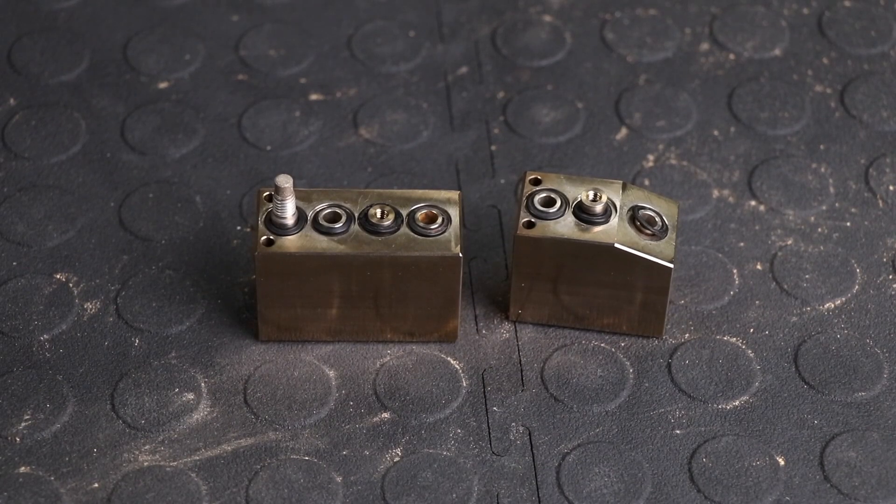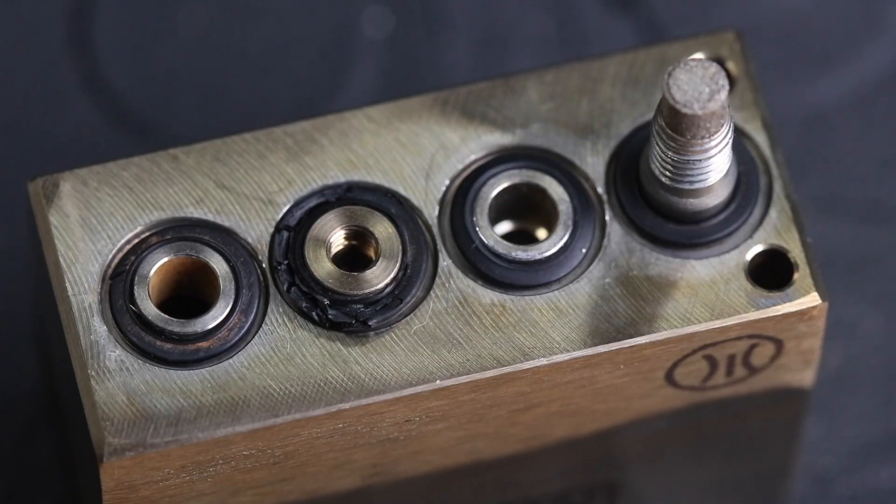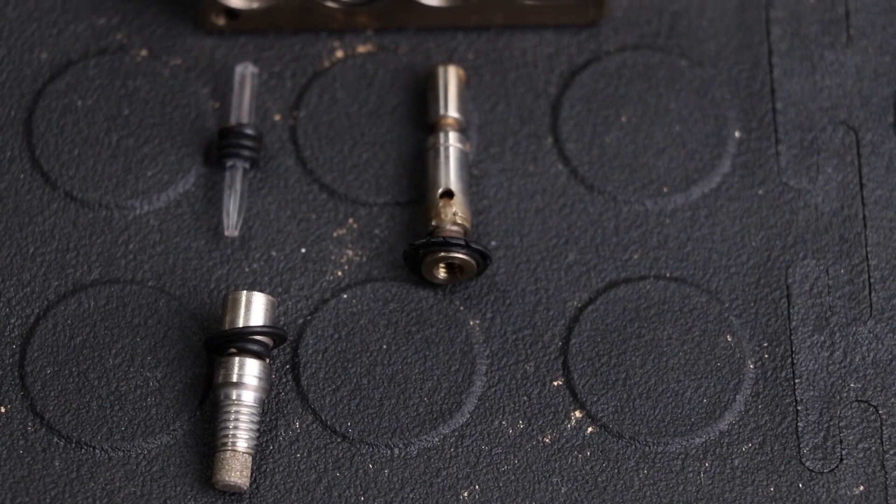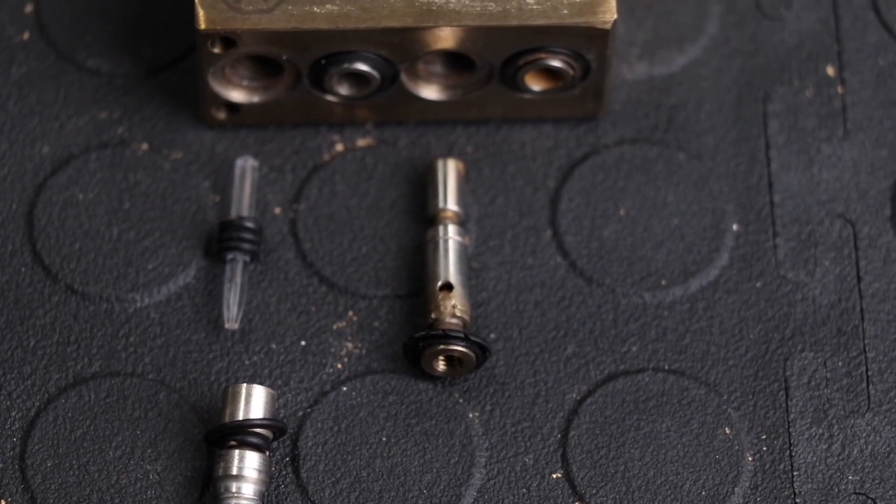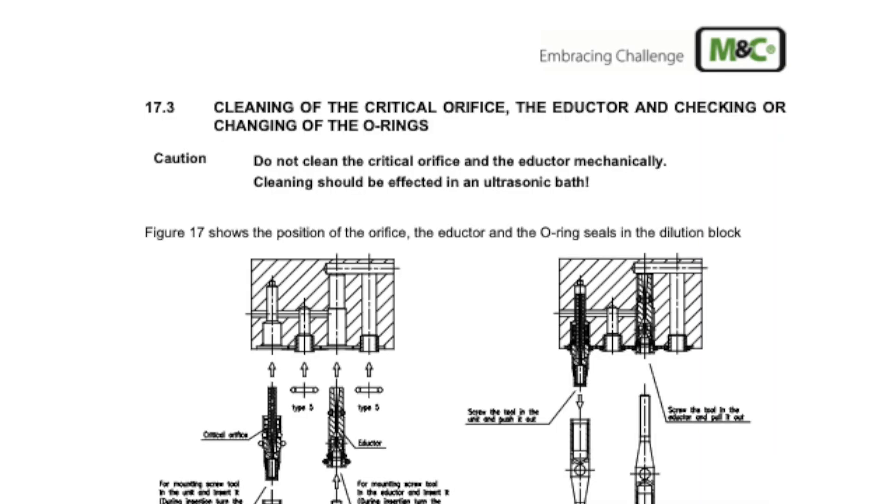Inspect the O-rings. If they are damaged or flattened, replace them. Use the provided tool to remove the critical orifice, eductor, and bypass eductor from the blocks. Refer to Chapter 17 in the user's manual for an exploded drawing of the equipment.